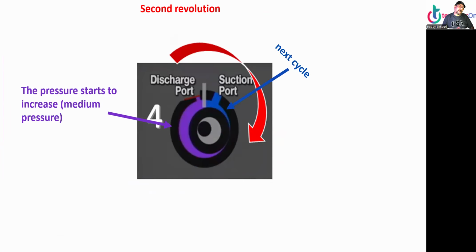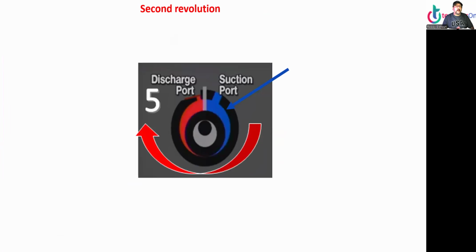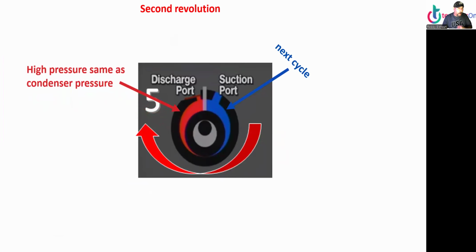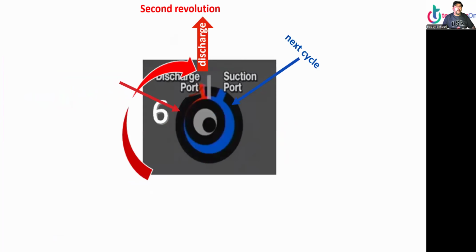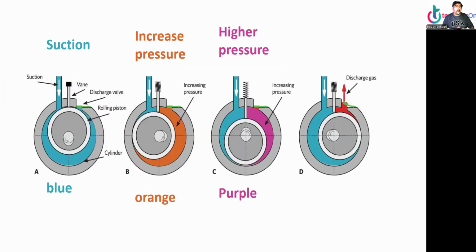And the blue is the following cycle. The blue is the next cycle. High pressure, same as the discharge pressure now. Now the chamber got smaller, squeezes more, and discharges. As it squeezes, it discharges at higher pressure than the condenser. Alrighty, so suction, increased pressure is orange, a little higher pressure is purple, and then discharge pressure.